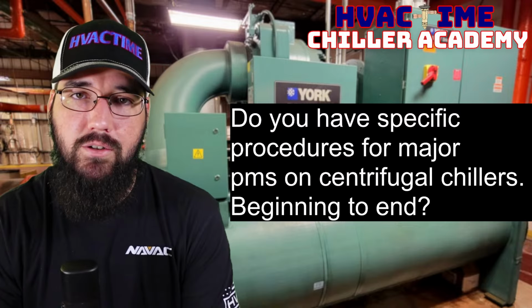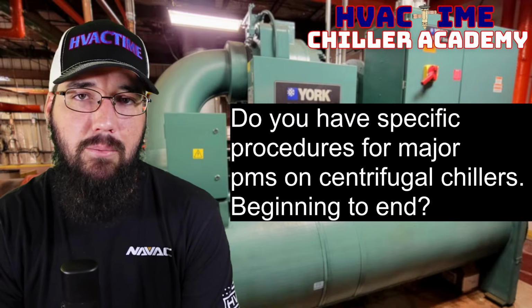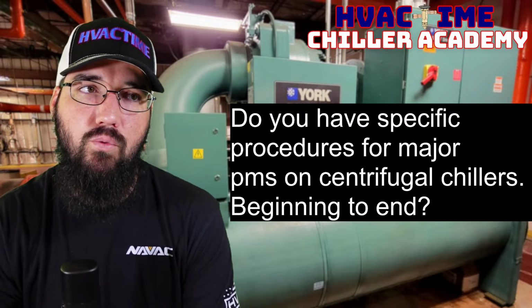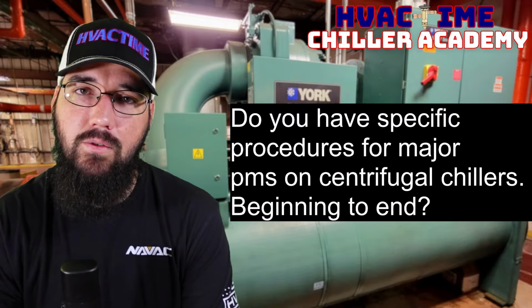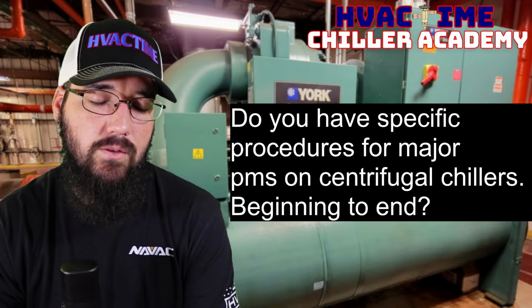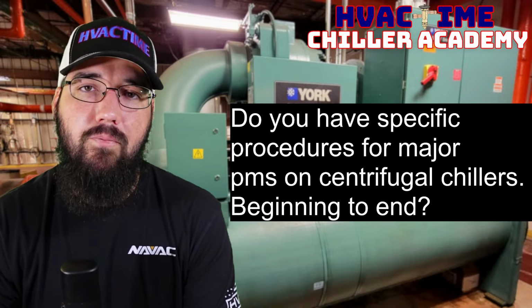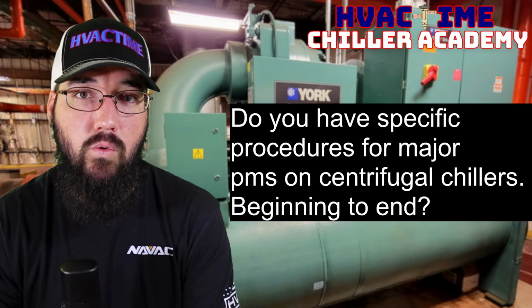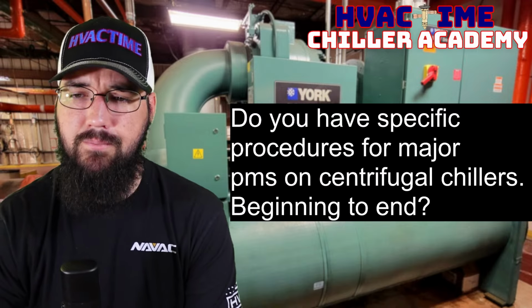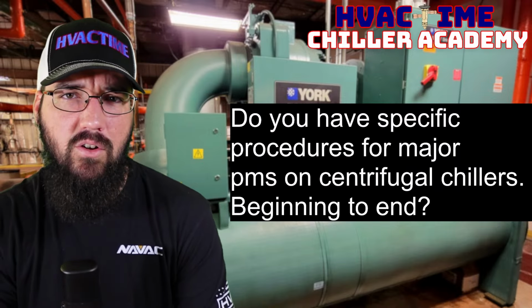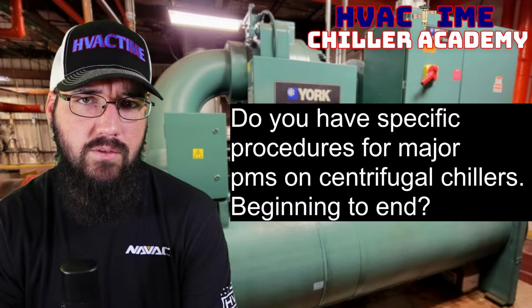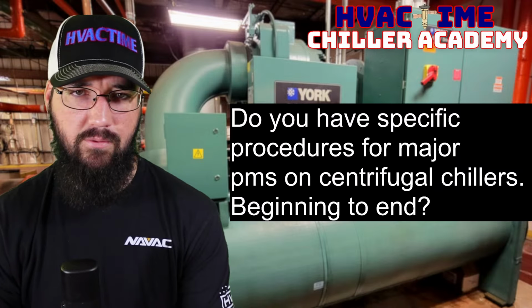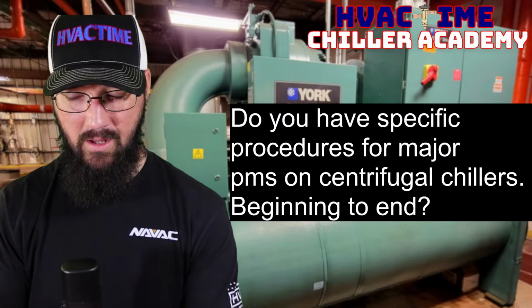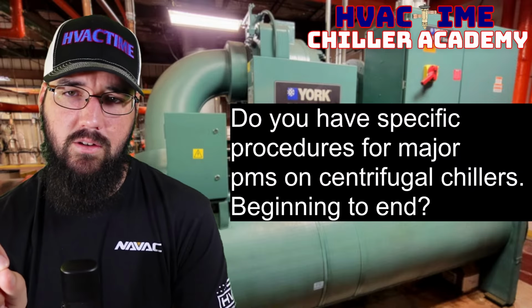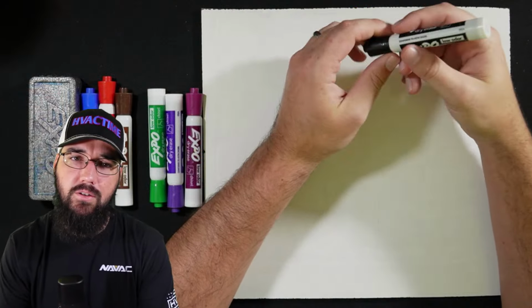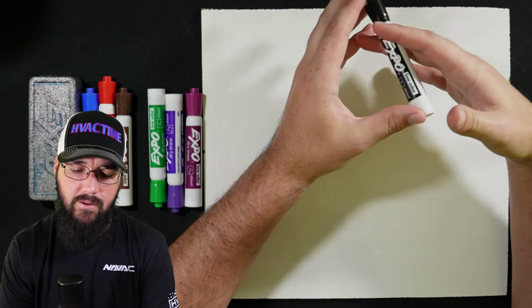That means we have to pressurize it to at least 5 to 8 psi, which is pretty typical. I really don't recommend pushing up to 10 or more, because 15 is when you start rupturing burst discs and bad things start to happen. So 5 to 8 psi is pretty normal for pressurizing a low pressure machine. A lot of things scale from low pressure to high pressure. It's still the basic flow, and we can draw out what that flow looks like for me.